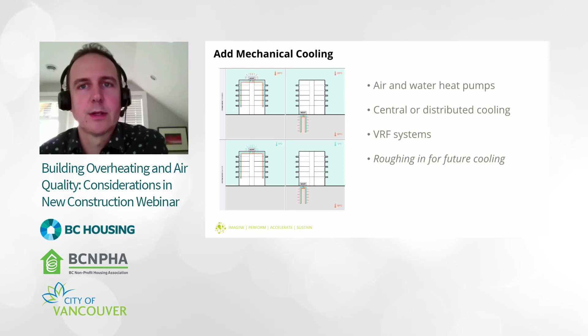How you distribute cooling can actually have a big impact on the capital cost. Again, if it's centralized, it can be fairly cost effective. You're providing cooling from a single unit. The level of control needs to be considered. Different elevations will experience different degrees of thermal comfort or overheating potentially, primarily based on the position of the sun. So understanding control on a central system and how it can be implemented in a cost-effective manner is something to think about. And then you have moving away from a central model to a distributed one, where you provide cooling more on a space-by-space level.